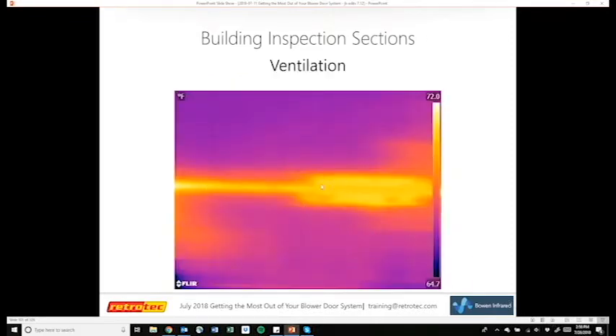And here we have one more ventilation issue. Here we're on a ceiling. The duct is a round duct going through a joist cavity from one side of the room to the other. And then we see this large bloom of air spilling onto the backside of the drywall on the ceiling. And that's being caused by ductwork that's not sealed at the joints. And air is pouring out of that duct and actually warming this airspace within the joist cavity. So the air is not getting where it belongs.